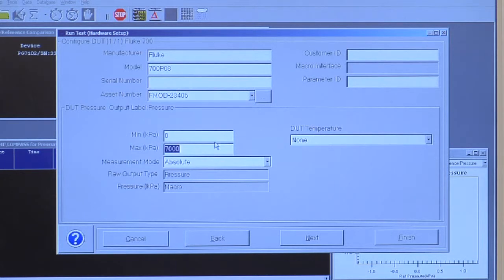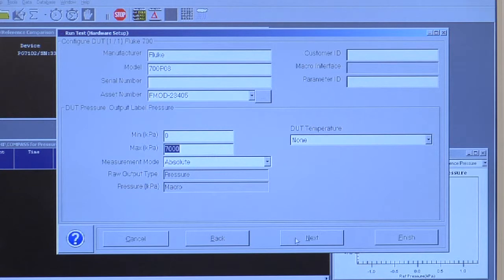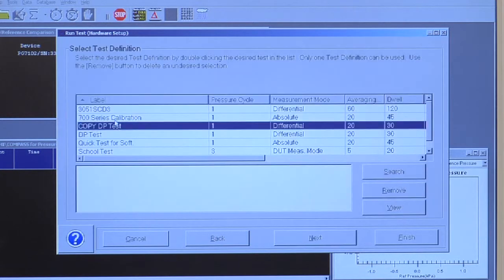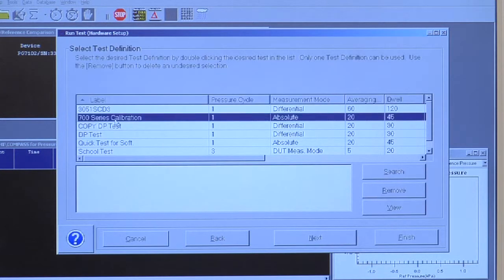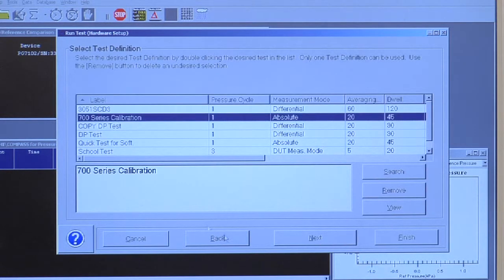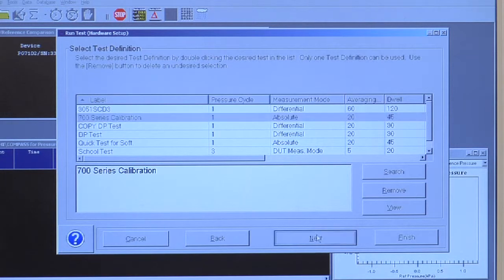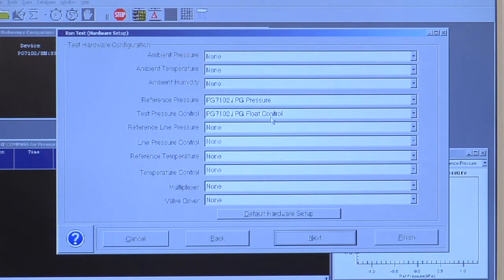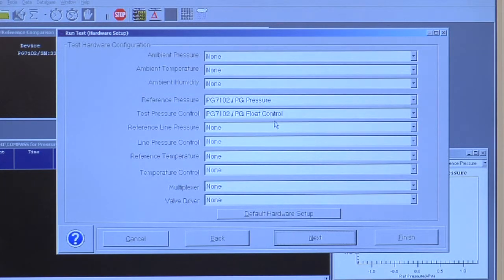The pressure range in my example is 7 MPa. Here's the test definition that I used earlier. It's a little overkill, but I am going to use a piston gauge to calibrate the pressure module.